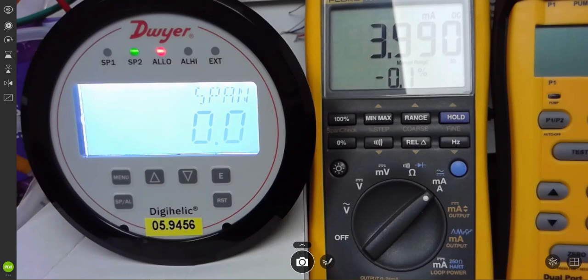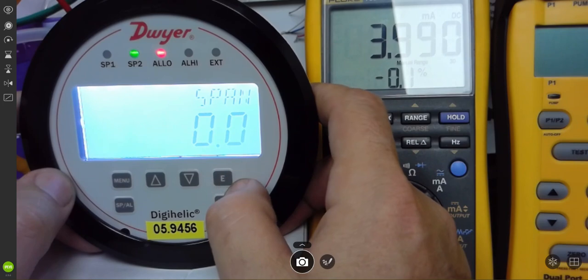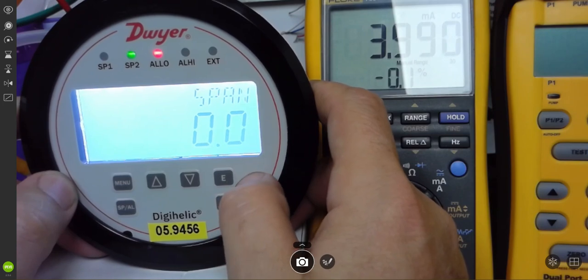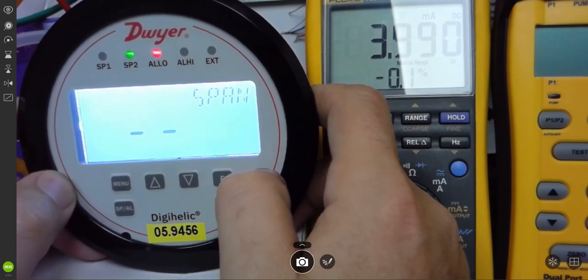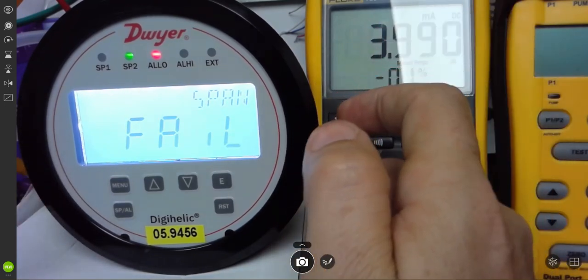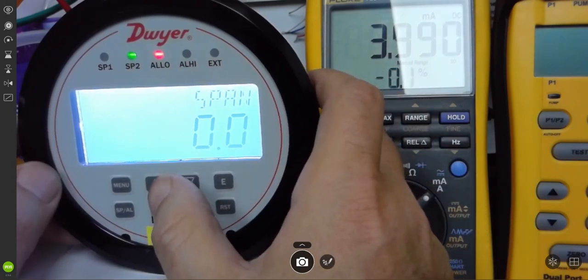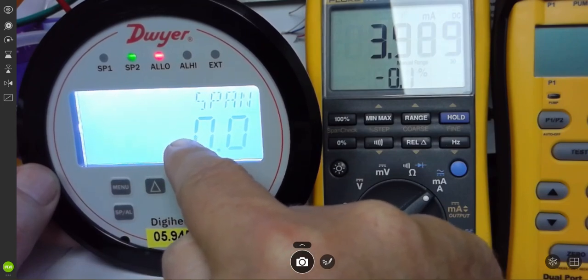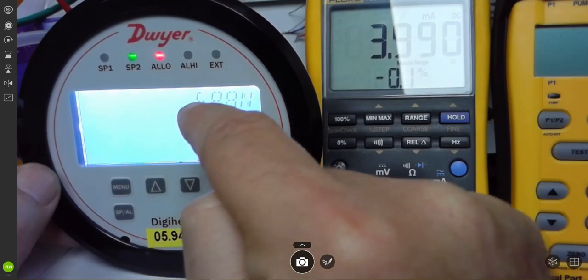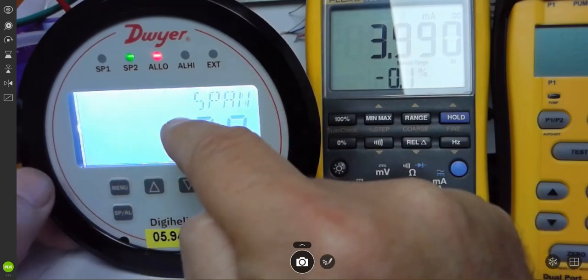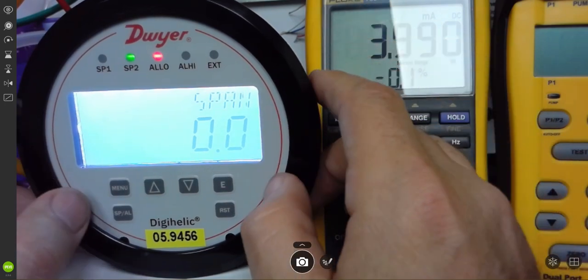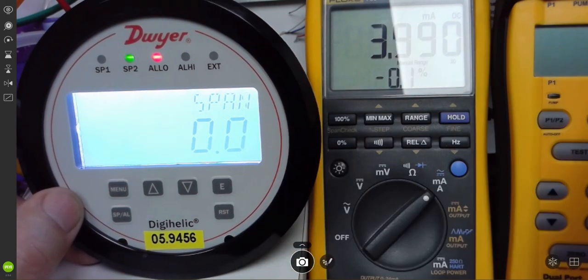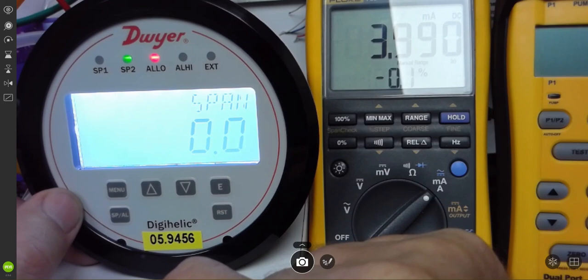If so, it's pretty easy to do from this menu. Watching this video, I would simply, if I was going to do that, I'm not really going to do it. But I would go in here and I would hit span, which is zeroed now, which is fine. We'd hit enter. If there's nothing on there, it's zeroed. That's fine. But I believe the span is the high side. So I zeroed it. And now I would need to run this up to 50 inches of water column. And if it was anywhere close to 50 inches of water column and I hit that button, it would go ahead and recalibrate. But it fails because I don't have my pump on. But we're not going to do that because we want to keep the calibration settings that were done at the factory. But that is how you would do it on the line if that is what they choose to do later on. I would run this one up to 50 and just hit that button on the high end after I zeroed and I would be done.